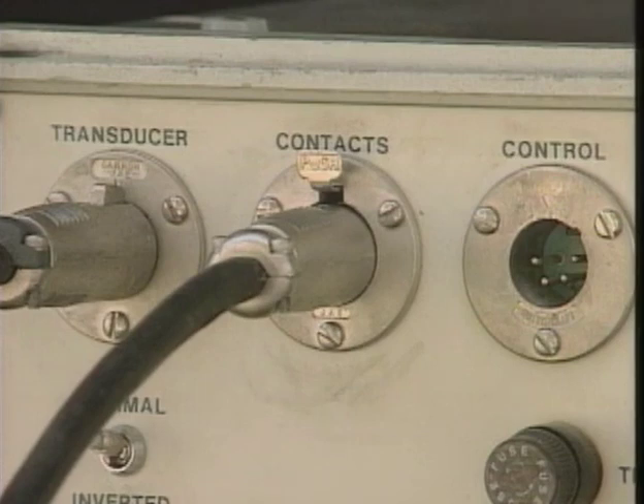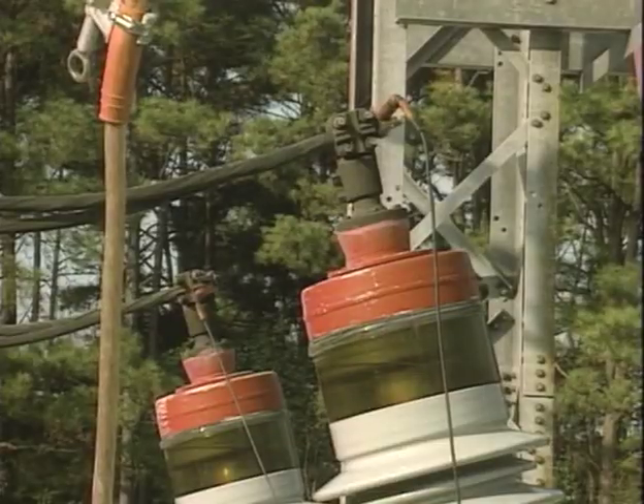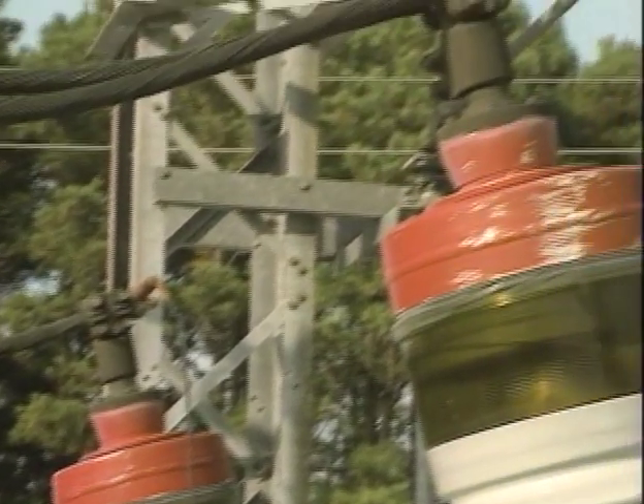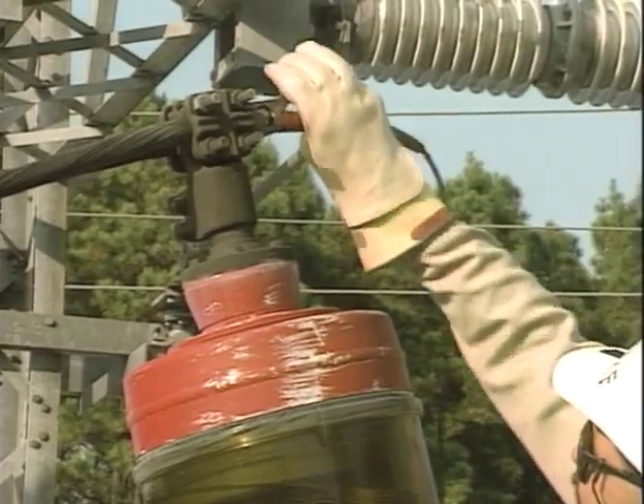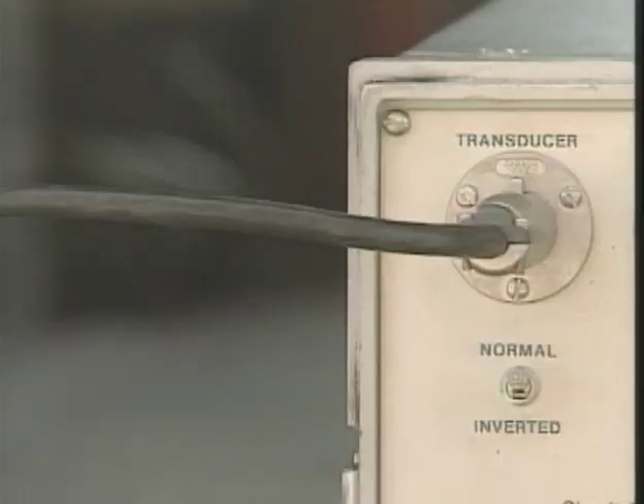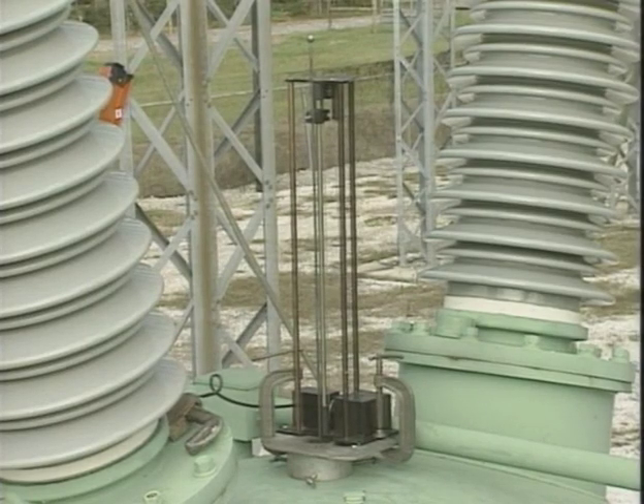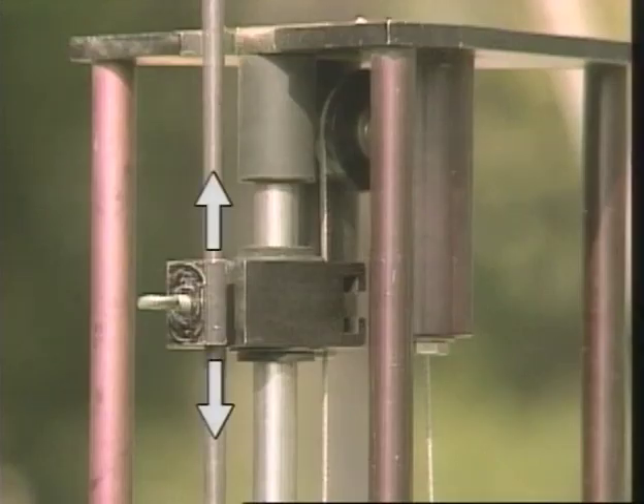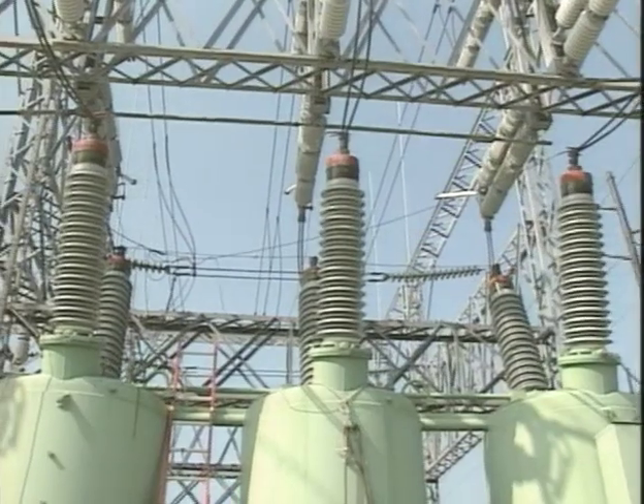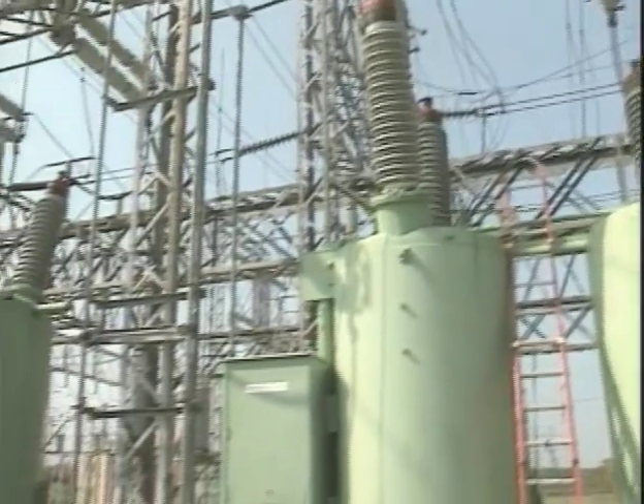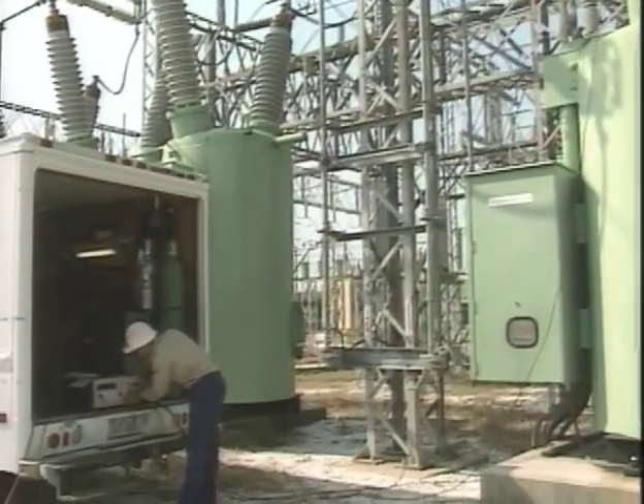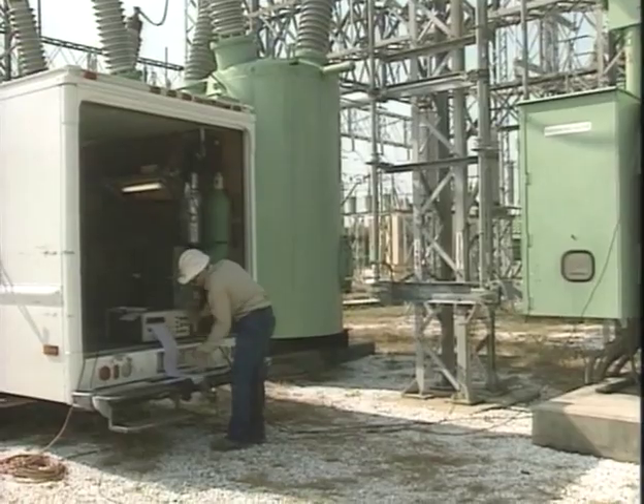For the timing part of the test, contact test cables are connected from the test instrument across the breaker's contact terminals to determine when the breaker contacts open and close. For the travel part of the test, a cable is connected from the test instrument to a mechanism called a transducer. The transducer is connected to the breaker's operating rod to detect the movement or travel of the operating rod when the breaker is operated. When the breaker is operated for the test, the time travel test instrument draws lines or traces on a moving sheet of paper.